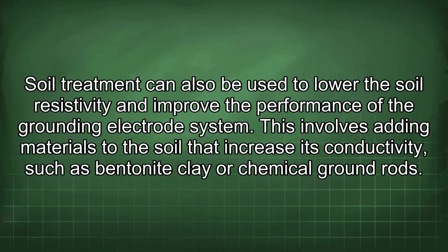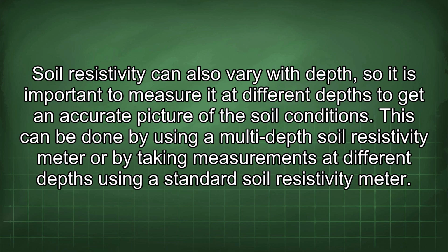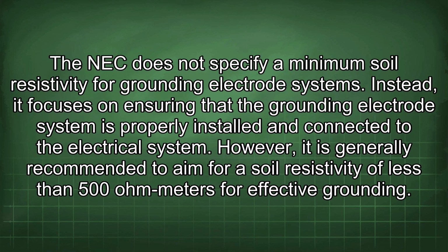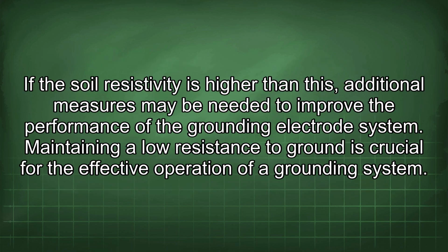Soil treatment can also be used to lower the soil resistivity and improve the performance of the grounding electrode system. This involves adding materials to the soil that increase its conductivity, such as bentonite clay or chemical ground rods. Soil resistivity can also vary with depth, so it is important to measure it at different depths to get an accurate picture of the soil conditions. This can be done by using a multi-depth soil resistivity meter or by taking measurements at different depths using a standard soil resistivity meter. The NEC does not specify a minimum soil resistivity for grounding electrode systems. Instead, it focuses on ensuring that the grounding electrode system is properly installed and connected to the electrical system. However, it is generally recommended to aim for a soil resistivity of less than 500 ohm meters for effective grounding.